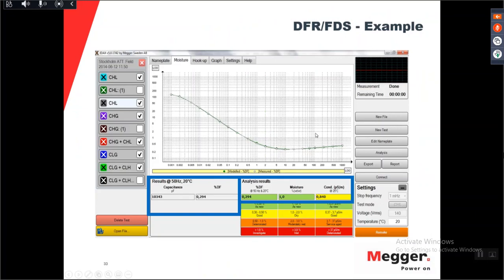I start by showing you a measurement example. So what you get is tan delta. Here you see tan delta at 50 Hertz, because this is frequency, 1 millihertz to 1000 Hertz, 1 kilohertz. The 50 Hertz is something that has been measured for 100 years now. So this is a typical measurement that you have seen. This is the basic test. You measure the capacitance and you get the dissipation factor, or the tan delta value.